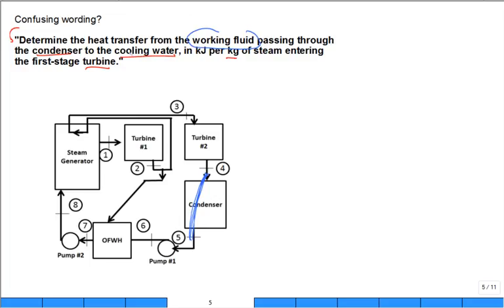But then we also have cooling water going in and out of this condenser. What's that? You may have a lake, and that's actually where the heat is being rejected to, in the heat exchanger called the condenser. So the lake water is the cooling water, and it comes in maybe 20 degrees C and goes out 30 degrees C. See, the cooling water is not the same as the working fluid. That's the first big distinction.